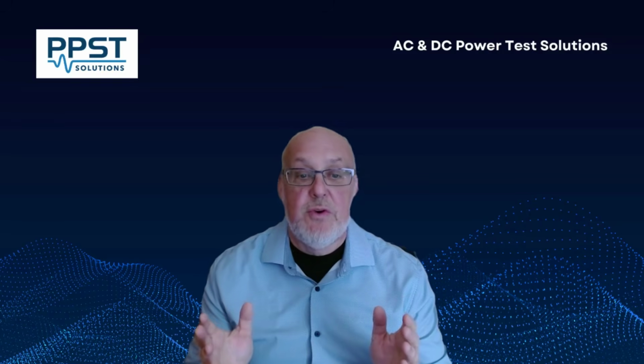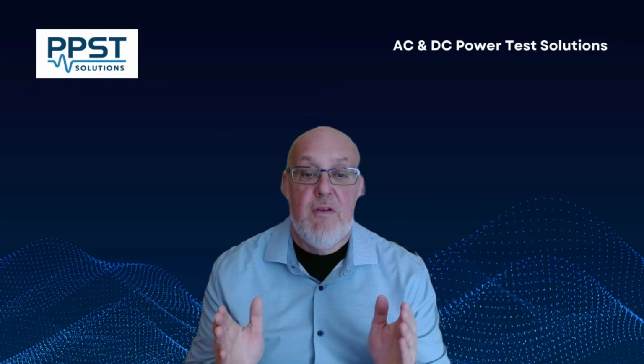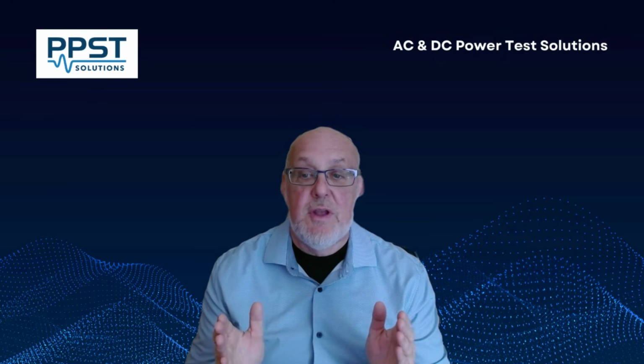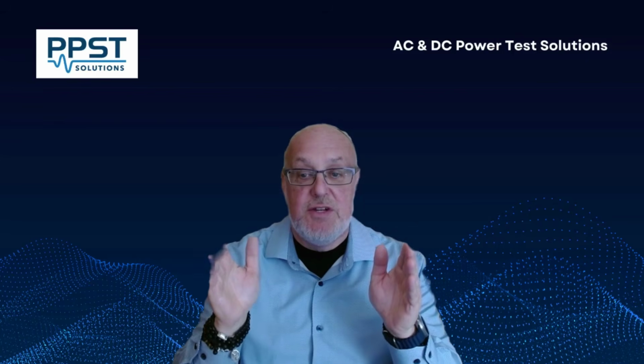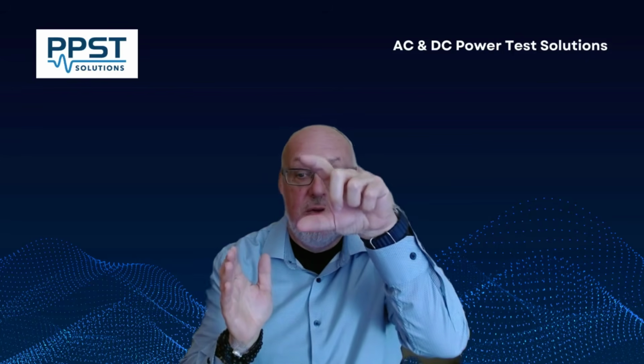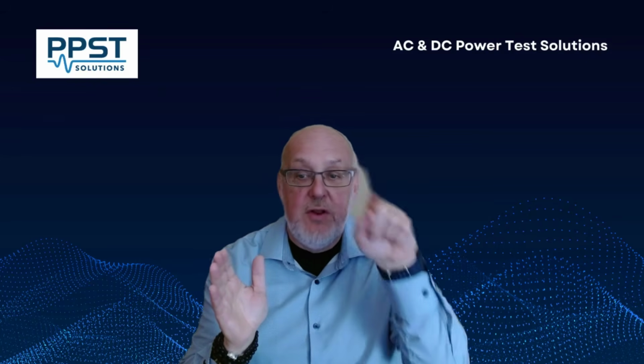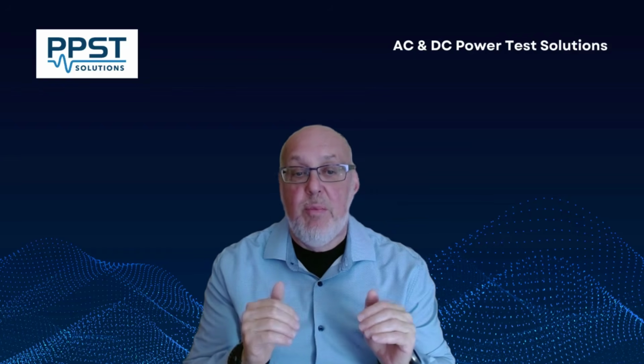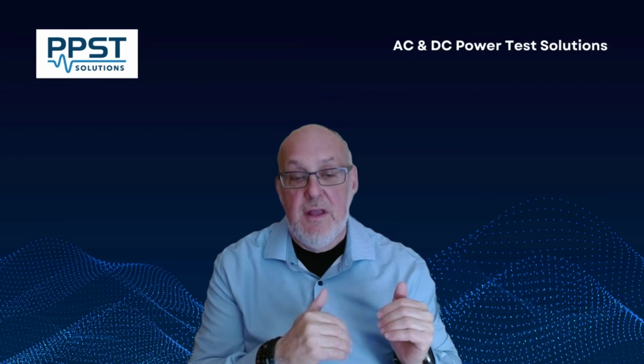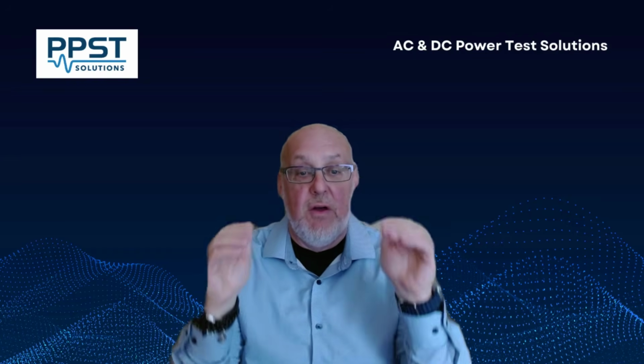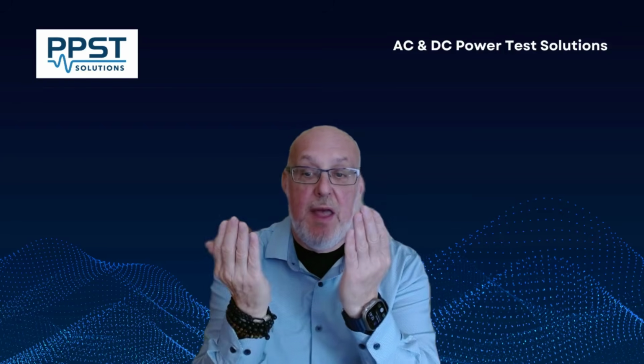So the picture that we're drawing here is, when you look at it from an energy loss perspective, you're just looking at the losses of the two energy devices that we have and the unit under test. And when you do that, all you're paying for from the utility is the energy losses, and all those sum together. So ideally, in our case, we're going back to back.